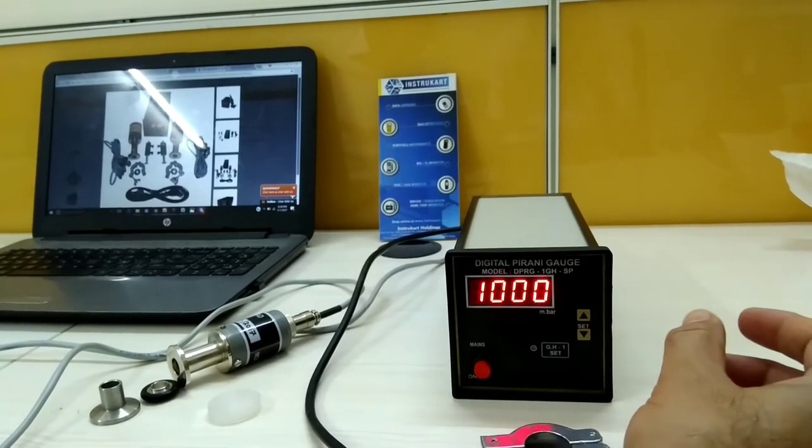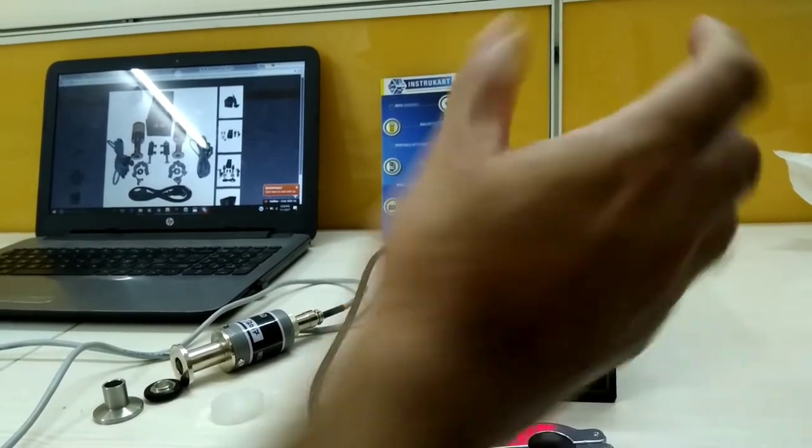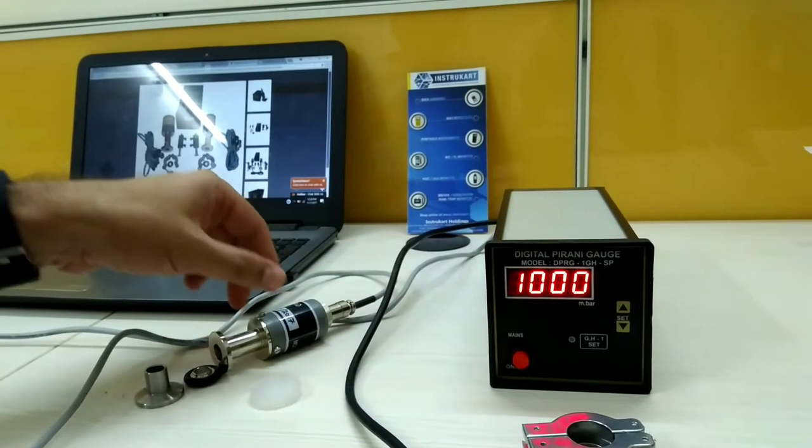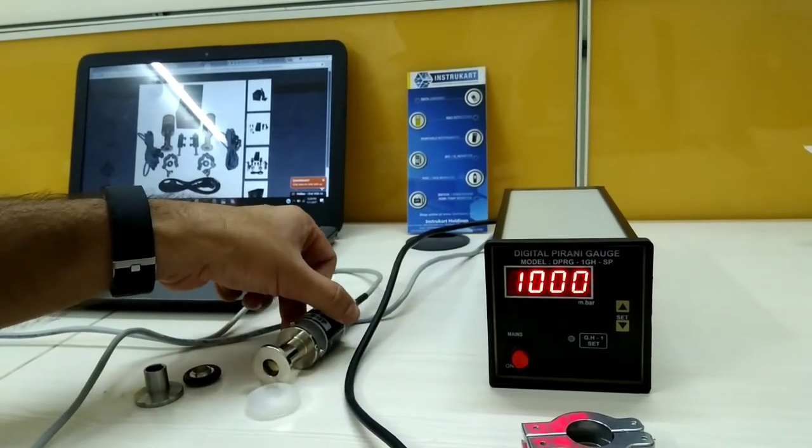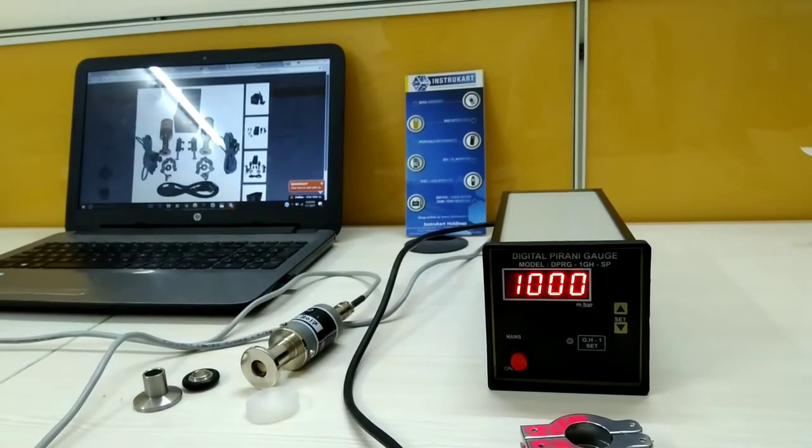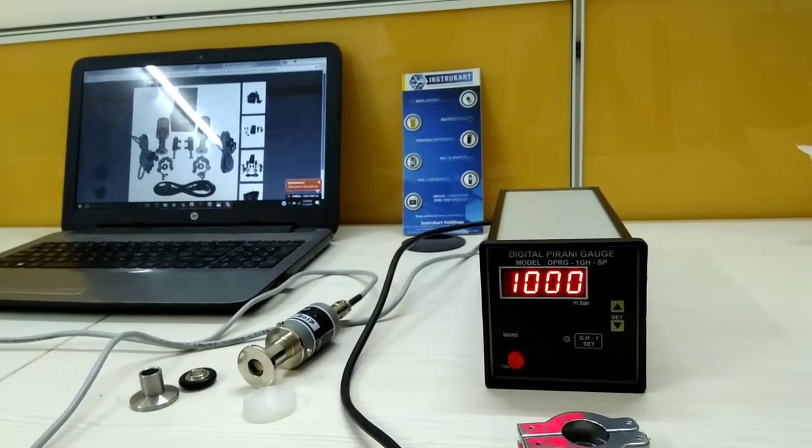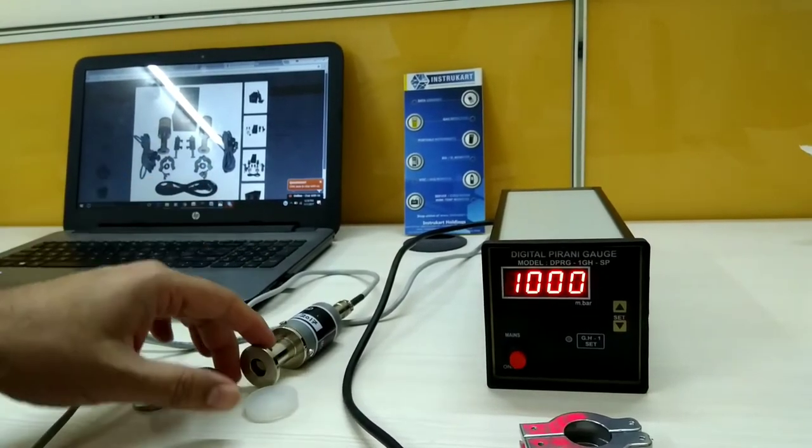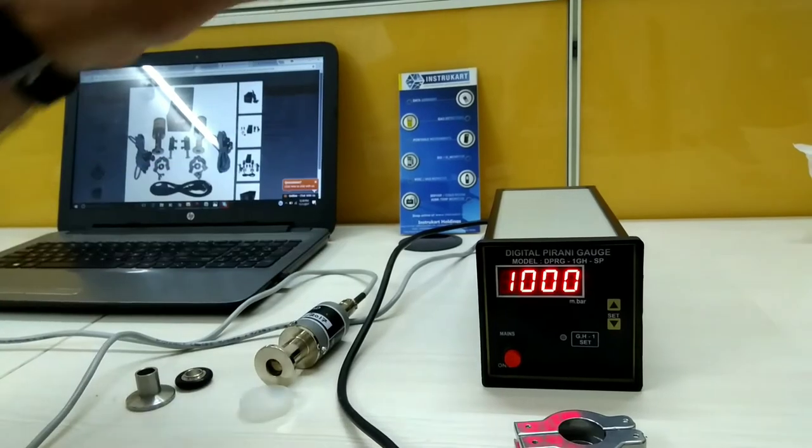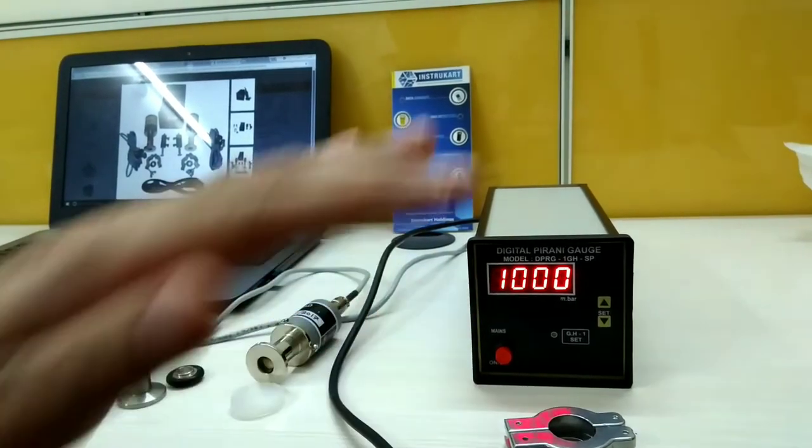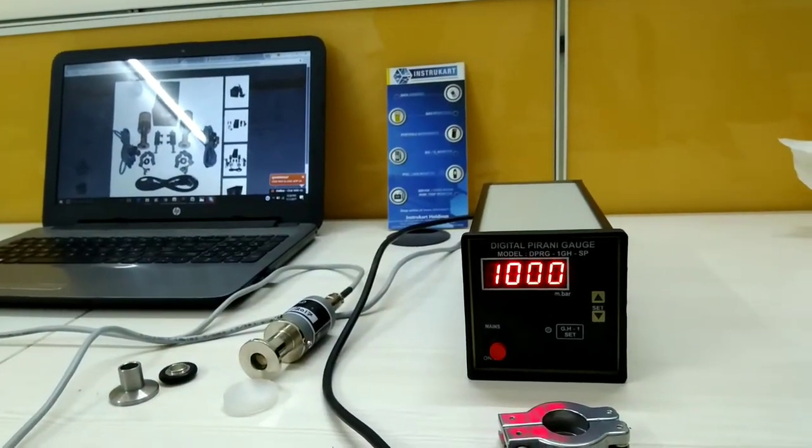It's a simple operation when I'm switching on the instrument for the very first time. I press the mains button and it switches on. This is the atmospheric or barometric pressure, it always indicates 1000 millibar in open condition. As we start vacuumizing the system where the Pirani Gauge Head is fitted, the reading goes down right up till 0.001 millibar, that is 10 to the power minus 3 millibar.